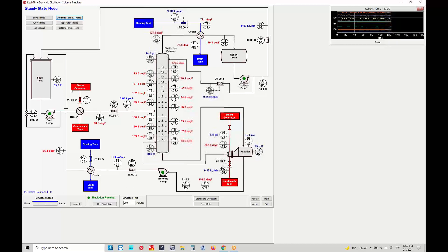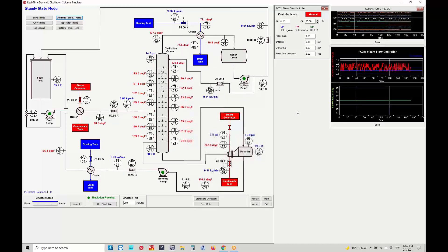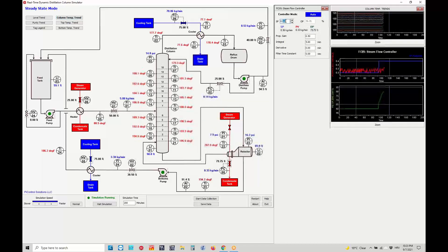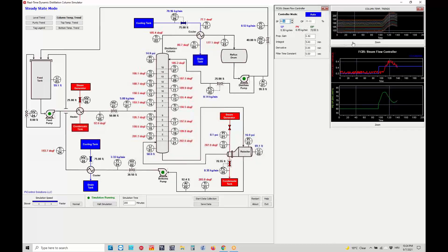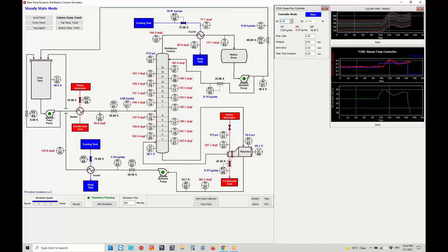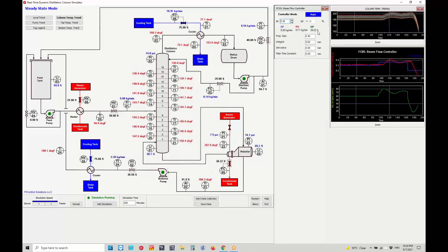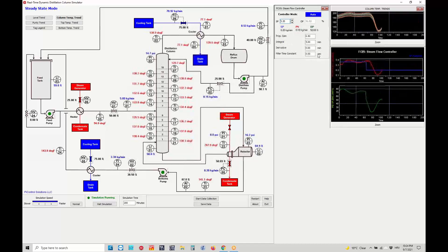You can see the bottom flow and the heater is open and active, so all things are running. If you click on the reboiler flow controller, you can change it from manual to automatic, and instead of changing the controller output you can change just the controller set point — for example, from 0.3 to 0.2 — and the controller will do the remaining job if it is well tuned. You can also tune the controller by adjusting proportional, integral, and derivative parameters to make the stability of controls much better.